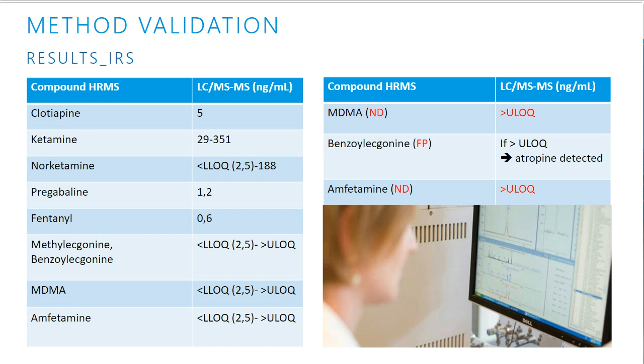However, what we also observed when analyzing authentic samples was that some, for example, you see on the right-hand column the MDMA, was not detected because we had such high concentrations. So there was a kind of saturation, and according to our identification criteria, this was not a peak that was of interest. So what we do now is that we are going to inject the same extract, but once 1 microliter and 3 microliter. The 1 microliter kind of dilutes the sample, which makes the saturation less a problem. But on the other hand, we have the 3 microliter injection that gives us enough sensitivity for other possible compounds in the sample.